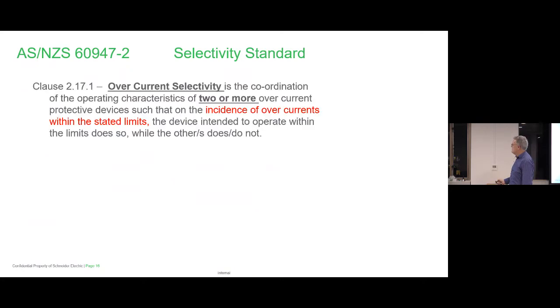Okay, so the standard, the AS/NZS 60947-2, is for circuit breakers, the selectivity standard. If you look at this statement in 2.1, it says overcurrent selectivity is the coordination of two or more overcurrent protective devices, such that on an incident of overcurrents within the stated limits, the device intended to operate within the limits does so, while the other does or does not. So meaning it might not. So this falls into that partial discrimination. They have to have a statement in there for that as well.